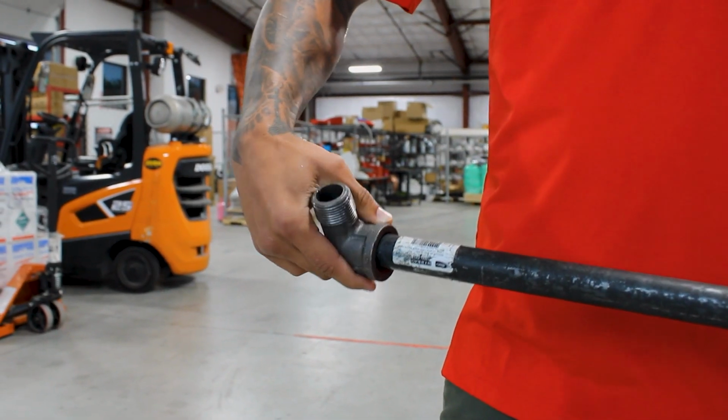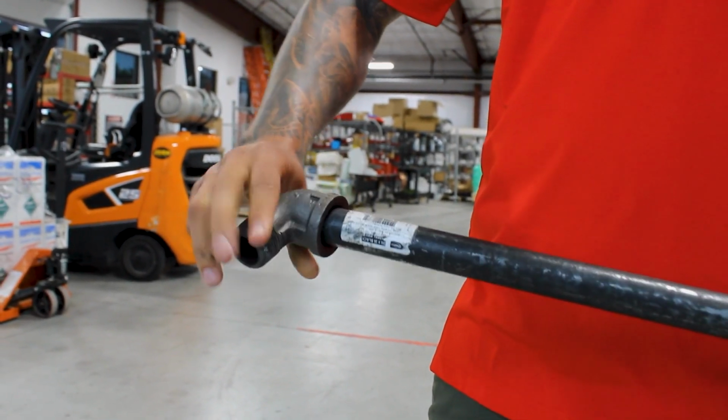There are certain homes that are trying to incorporate a flexible gas piping system. It's a little more complicated because it doesn't hold up well during lightning strikes, believe it or not. The flexible piping, I never recommend ever, honestly, because of that. I've seen it with my own two eyes.